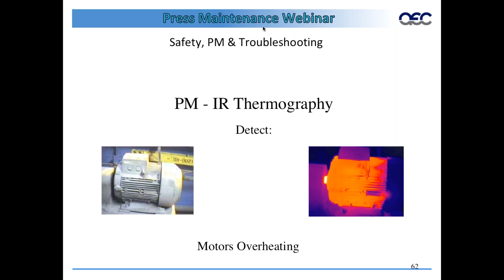Should it be? Well, here's a normal motor, a TEFC, meaning it's totally enclosed, but it's got a fan on the back. And that fan pulls in ambient air in through the cooling fins of the motor. It may have cooling fins or may not, but it moves air across the motor to dissipate the heat. Eventually, if you don't, then this will be the culprit. Mostly motors fail either from bearing life or from heat, and generally it's bearing life, which breaks down the insulation and causes failure. So you can go quickly over your whole plant. You can look at any motor, and you can see quickly if something doesn't look right.